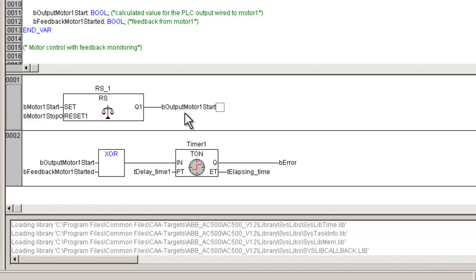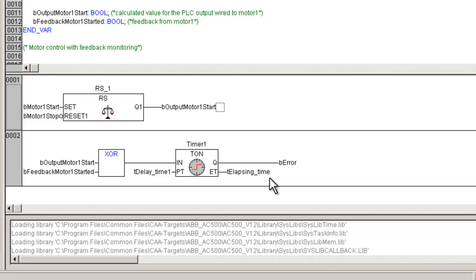The motor is started by pressing a normally open type start push button, and stopped by a normally closed type push button. The output of this logic drives the motor contactor, and there is a feedback from the motor to ensure correct operation in the field. If the motor contactor does not get energized within a stipulated time, the output logic will be made off to de-energize the motor. Therefore, we have three inputs and one output which would be simulated from the visualization screen.